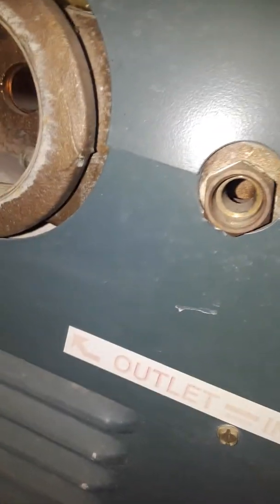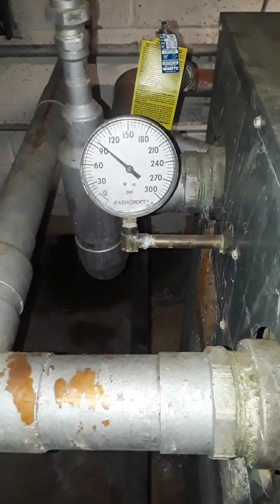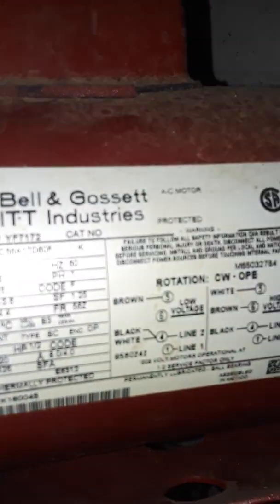There's a temperature sensor in there. There's a flow switch that was on the other one, and a temperature gauge port on that one. And then this operating limit — operating control, temperature control, limits inside. So, the pump — we need to duplicate this setup here.